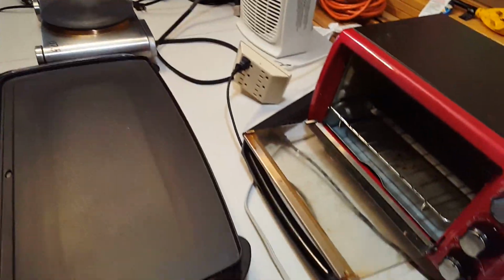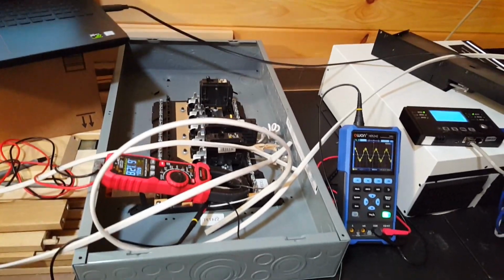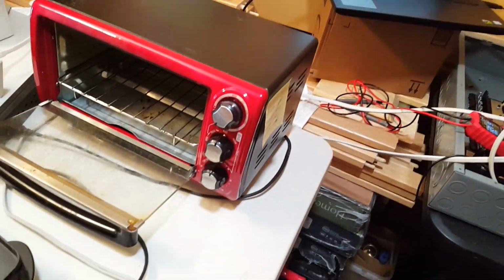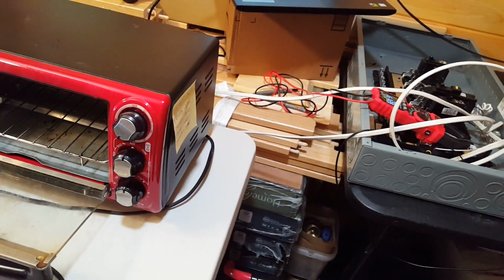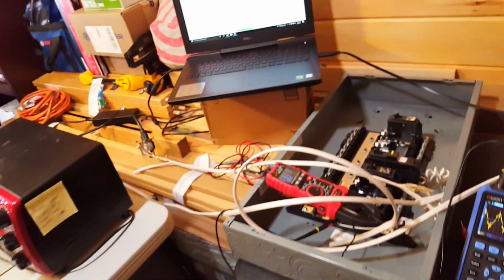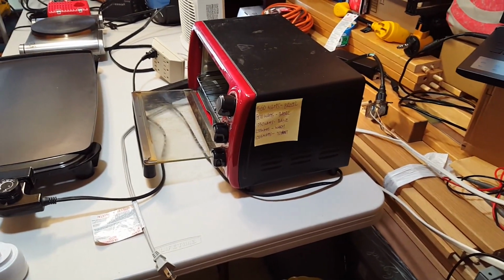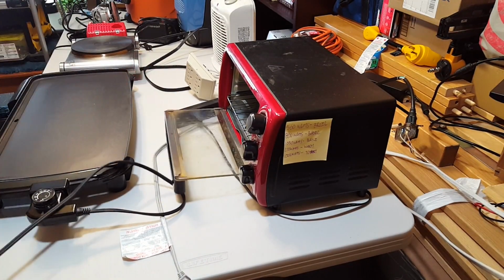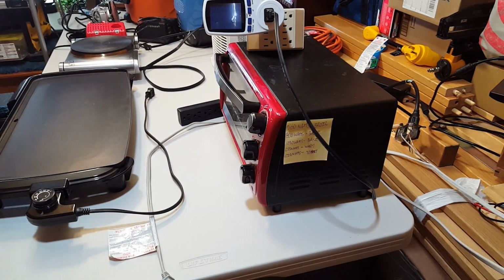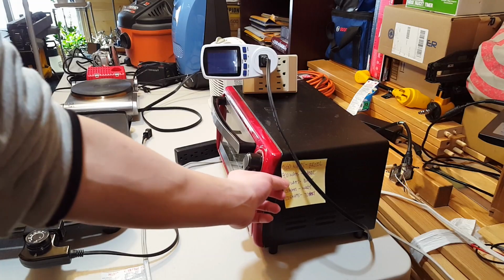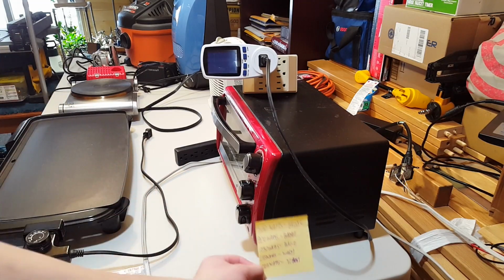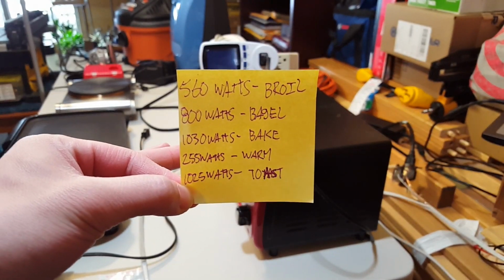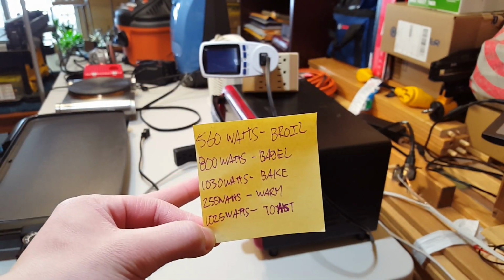So I first want to start with testing every single load individually on bypass mode, and then we'll switch each load individually over to battery mode and see if there's any differences in the wattage for the loads. We'll start with some of the space heater type of loads. A toaster oven. Now, a toaster oven has different settings on it. We're currently in bypass mode. If you can see this sheet of paper here, I've actually tested it prior. Here's the various different heat settings for this toaster oven and some of the wattages.